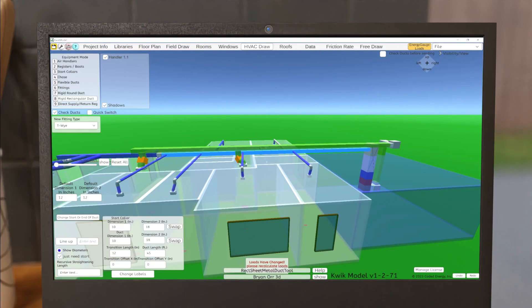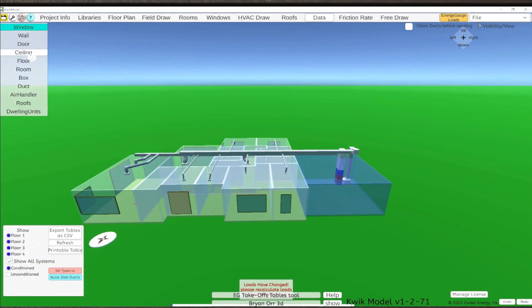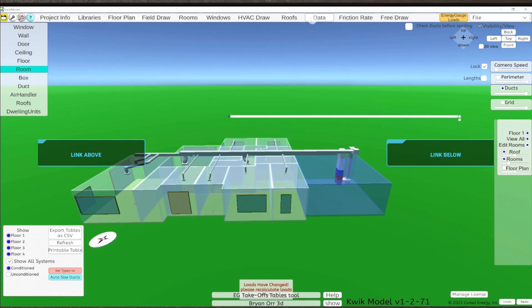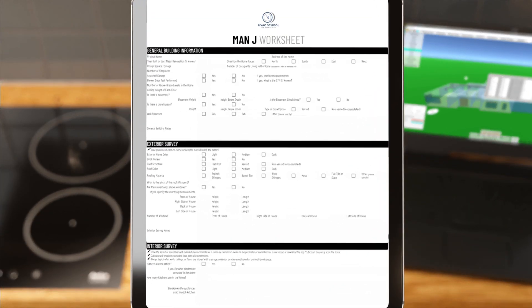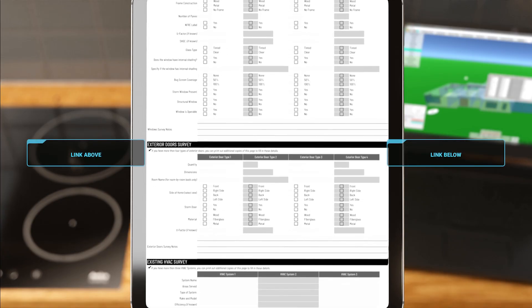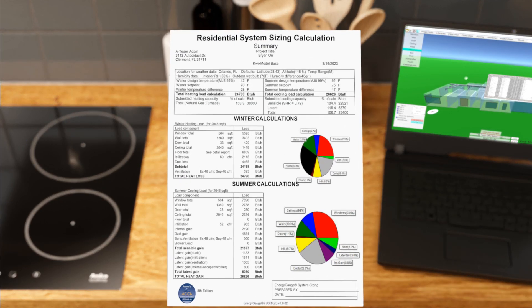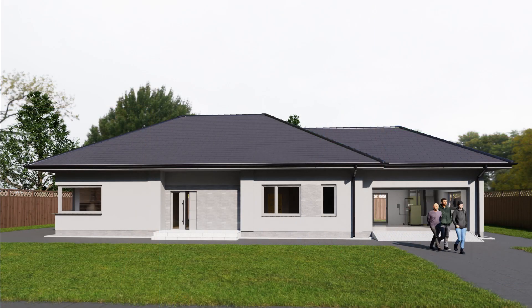Using all the data we've gathered, we can finally put it all together and finalize our load calculation. There are many types of software nowadays that can help you determine your heating and cooling loads — you can use any software you're comfortable with as long as it's ACCA approved. We've chosen to use Kwik Model with Energy Gauge loads for this video. This is how you collect data for a Manual J load calculation. Once you know your total heating and cooling loads, you can use those numbers to select your equipment. We'll be doing a 3D demonstration of equipment selection with Manual S, so be sure to keep an eye out for that video as well.